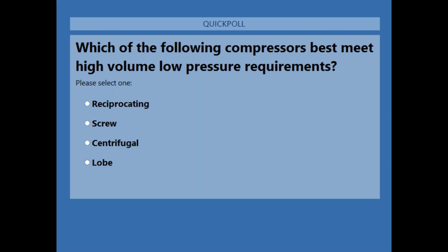I just discussed this concept of compressor selection, and still most of the students are saying we go for reciprocating. Remember that with a reciprocating compressor you'll get higher pressure. Whatever your pressure requirement is can be met by a reciprocating compressor, but not the volumetric requirement. If you require volume in lakhs of cfm, then you need a very big reciprocating compressor, which is not feasible. So the reciprocating compressor has a limitation of volumetric flow rate, not pressure but volumetric flow rate. Clear? Compared to centrifugal.